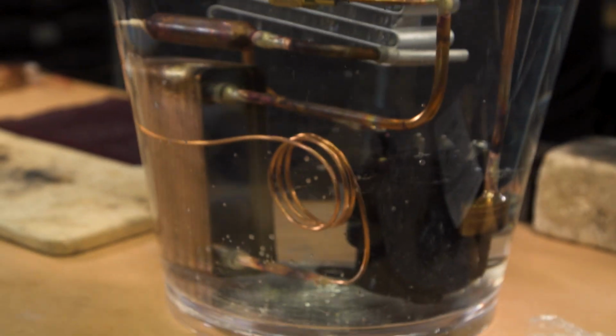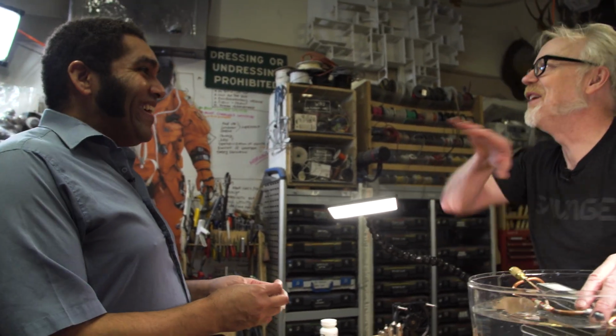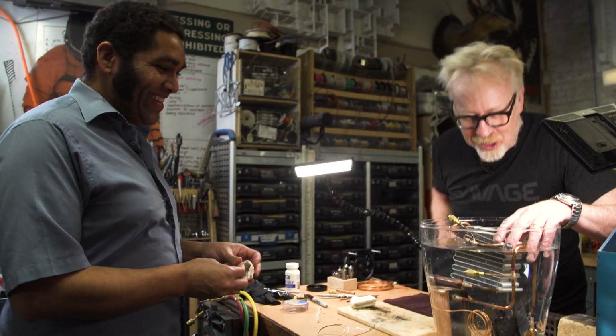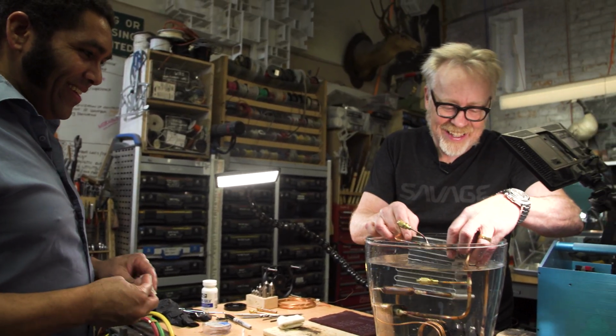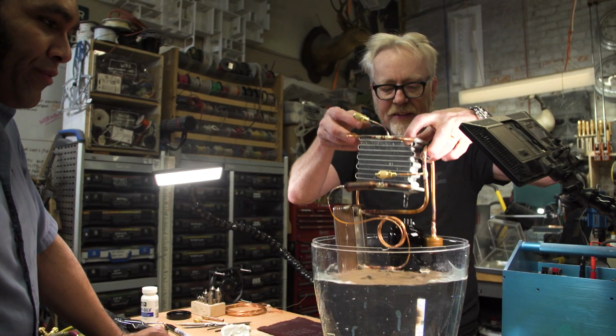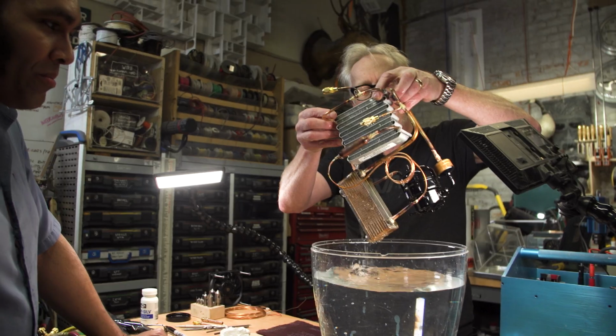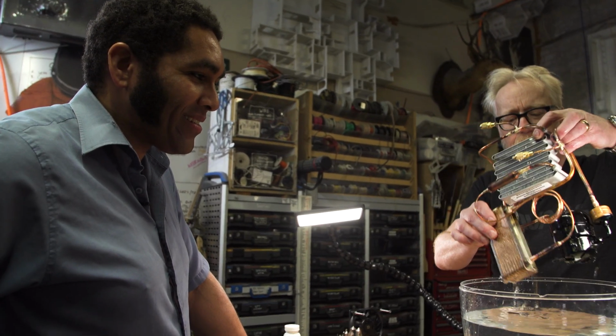Amazing. Dude, that's nuts. Our day could have gone any which way, right? This video could have been the first part of a video that's weeks long in the making, or we're done by the end of the day. That is awesome. So do we leave that in there for a while? No, we're good. We have a leak-free system. Leak test done. You have a hermetically sealed system as far as we know.